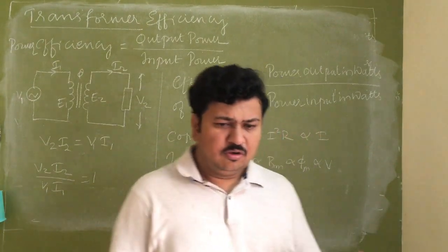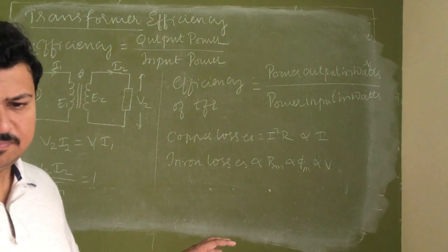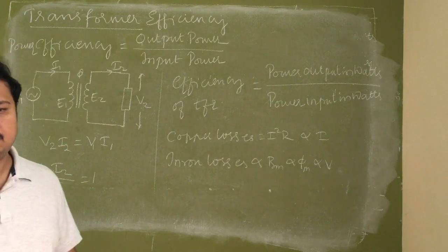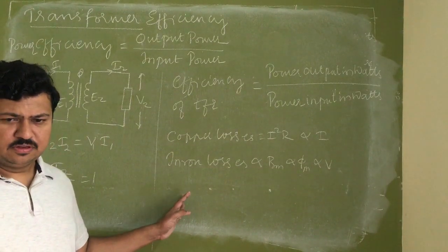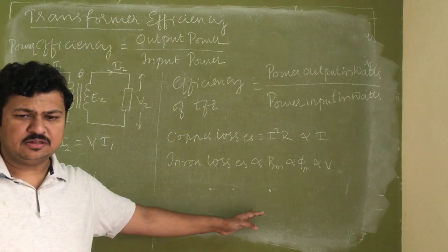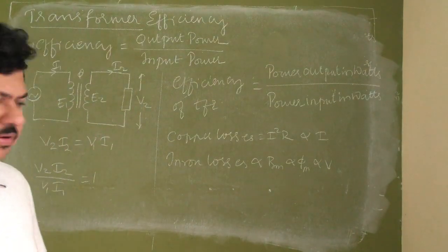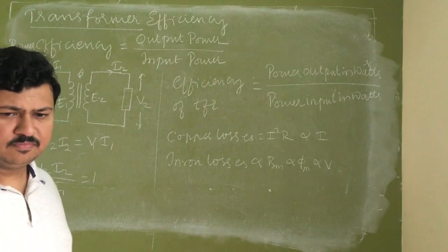So when I start that motor to lift the water, the operating power factor of that motor will be the power factor mentioned on the nameplate. So the input voltage is 230 volts multiplied by some value of current, into power factor, and that is my wattage rating, some 373 watts or so. Just now I told you that for a half HP motor it is so.